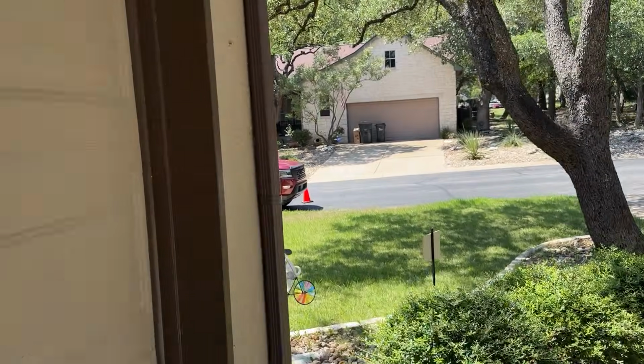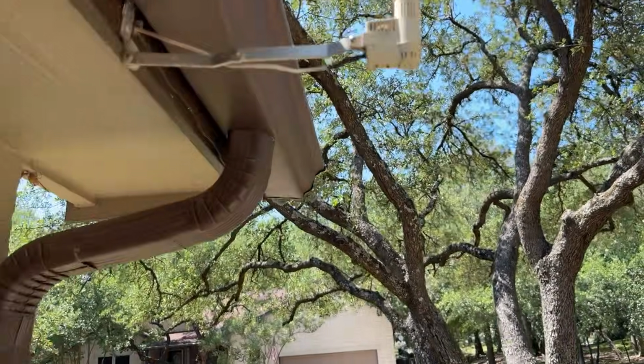So it will only leak when that zone is in operation, or any of the other zones. So again, if we don't see it on older systems, it's not necessarily a deficiency, but we make note of it, FYI, for older systems. So the next device we're looking at for our sprinkler system inspection is this guy.